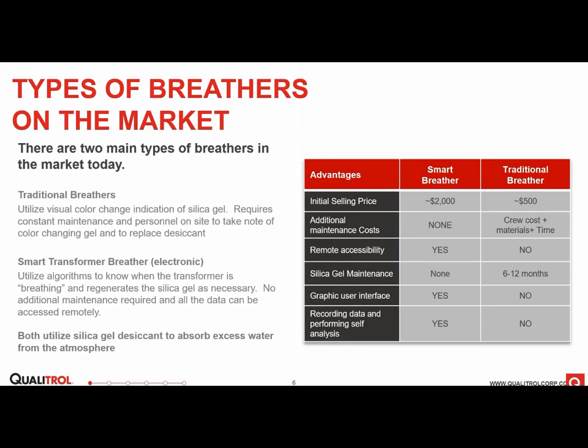So a smart transformer breather, or electronic or self-regenerating, are some of the terms that are thrown around there. The smart breather utilizes an algorithm to know when the transformer is breathing, and it will regenerate the silica gel automatically in a proper time window where the transformer is exhaling, and it can expel all the moisture out of the silica. So the silica can continue to dry the moist atmospheric air that's being inhaled into the transformer. One of the common traits between the traditional breather and the smart breather is that they both utilize a very similar silica gel to dry the air that is being passed into the transformer.